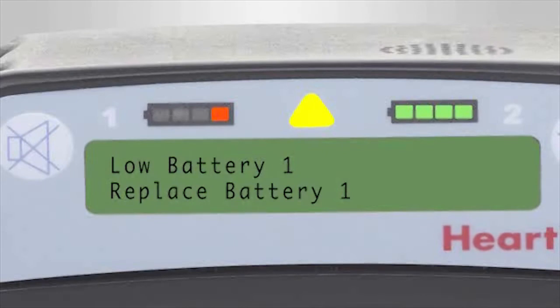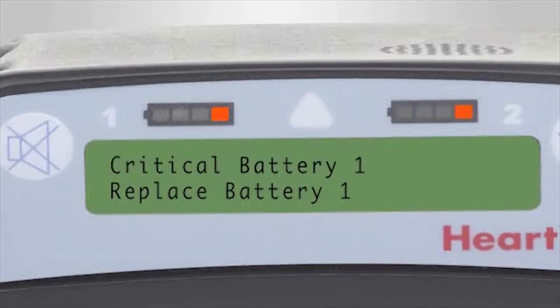a fully charged one. If a depleted battery is not exchanged and there are only a few minutes of battery time remaining in both batteries, a high priority alarm will sound, the alarm indicator will be flashing red, and the message on the controller display will read "critical battery." This means that only a few minutes of power remains before the pump stops. The batteries should be exchanged immediately.